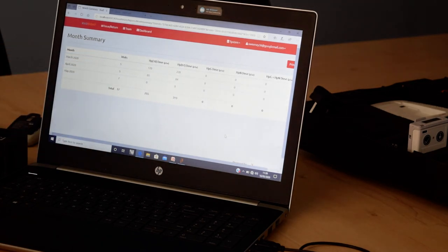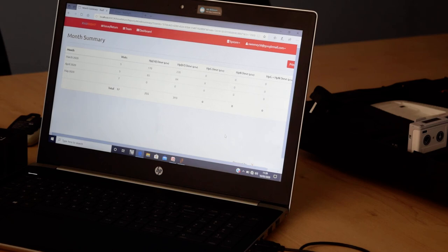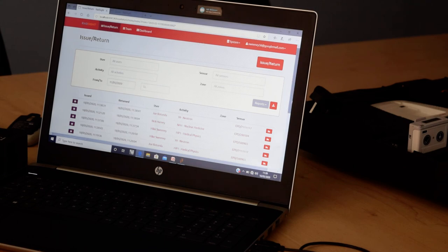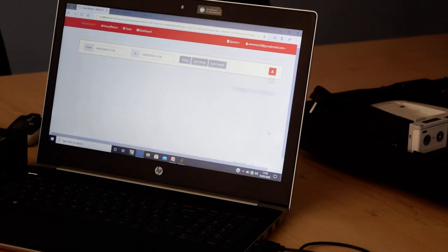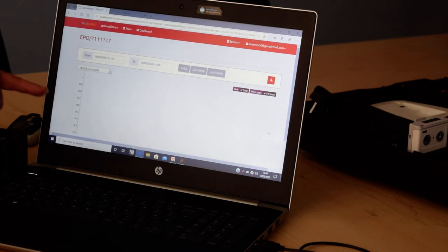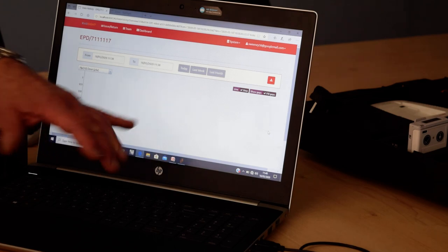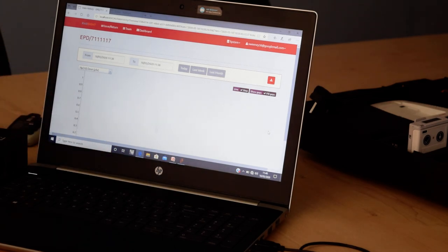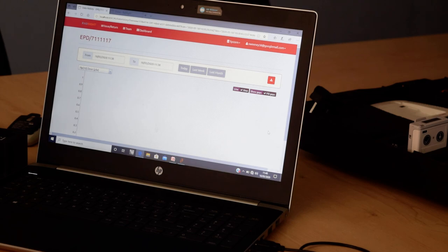At the bottom here, the cumulative doses, and all this data can be exported in spreadsheet form to another system. The dosimeter also stores graphical information as well, so if someone receives a dose, it's possible then to pull up a graph. It will actually show you a graph, showing you the peak dose and dose rate, and when someone had a radiation.